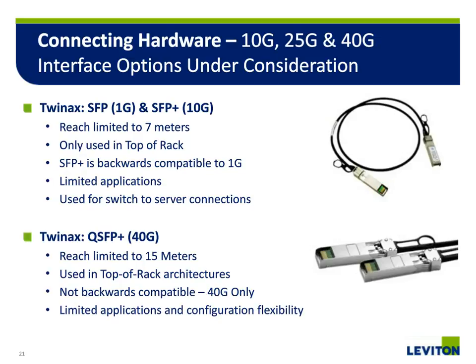This is an intelligent cable. There's a microprocessor and a circuit board inside of there. It is not considered structured cabling because you're directly connecting your switch to your server without any type of interconnect in between. Some of the challenges that you run into from a design standpoint is that the 1G and 10G are limited to 7 meters. The 40G could get up to 15 meters, but that's still a fairly significant limitation. If you remember, 80% of the switch-to-server connections run up to 30 meters. So beyond 15 meters, there's really not a good option for the direct-attached cable.